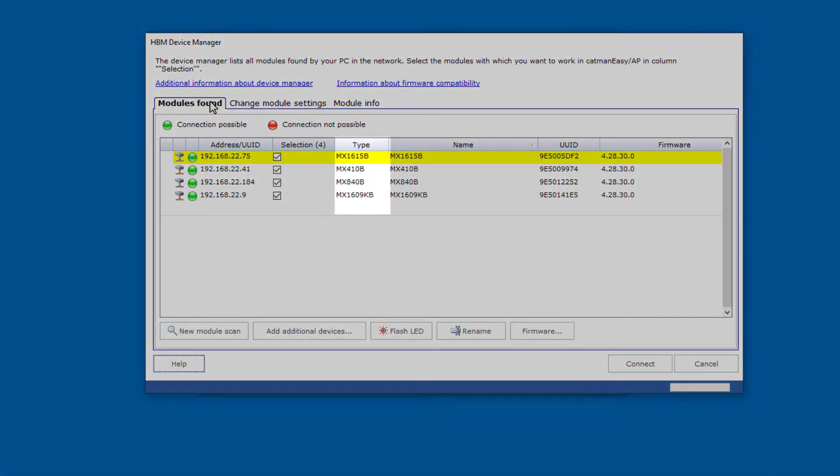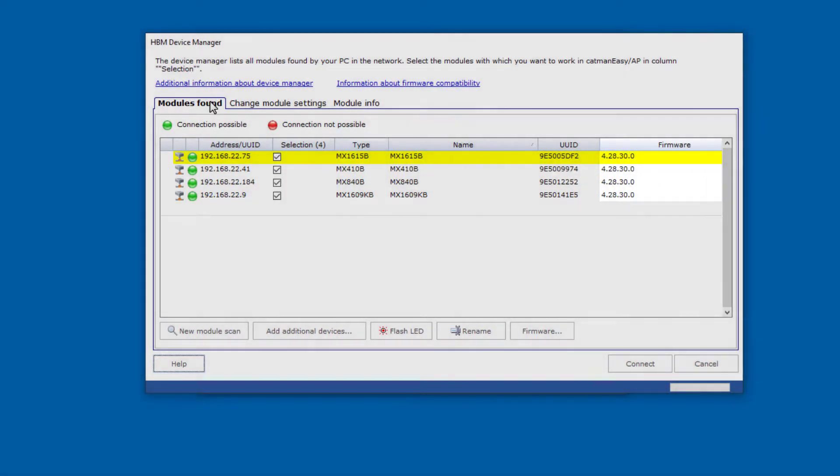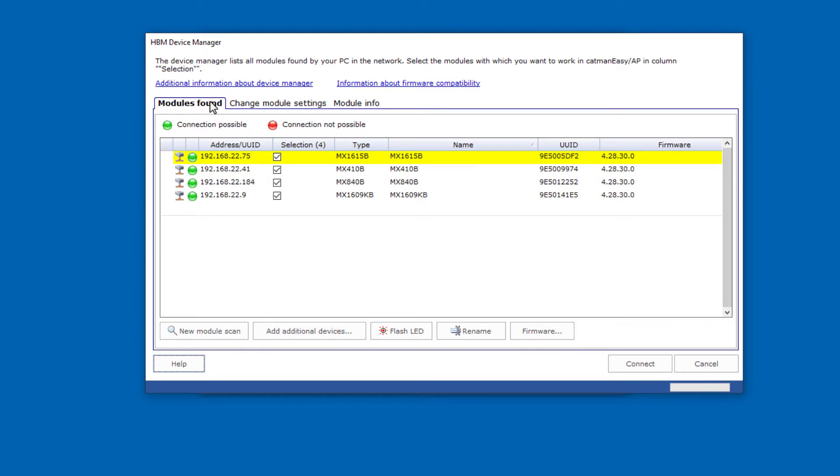Type, name, and firmware versions of the modules will also be displayed. Catman checks at each startup whether the firmware of its QuantumX modules matches the respective Catman version. If not, Catman also has the right firmware version for your QuantumX. If the firmware in one of the modules is not up to date, you can start the update directly from Catman using this button.